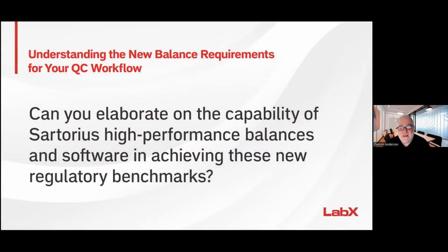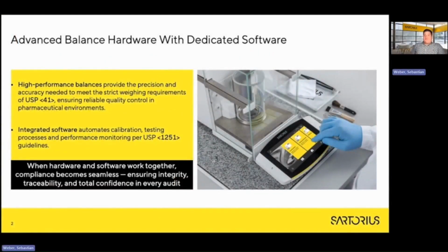Sebastian, can you elaborate on the capability of Sartorius high-performance balances and software in achieving these new regulatory benchmarks? The main idea of the combination hardware plus software is we have a high-performance balance hardware that delivers stable, precise results to meet USP 41, and the software puts USP 1251 into action, guiding the user on the balance screen and forcing the right steps in tasks like calibration, but also in the daily weighing, and recording everything electronically for simple and reliable compliance.